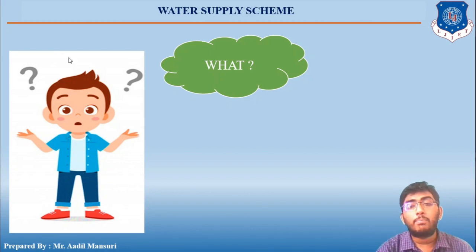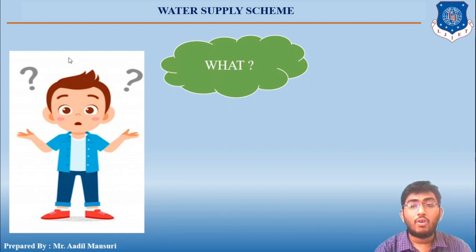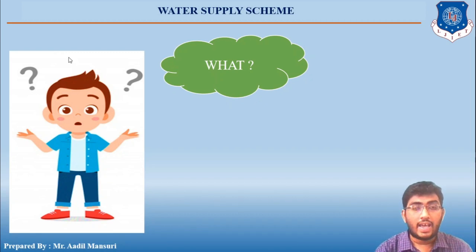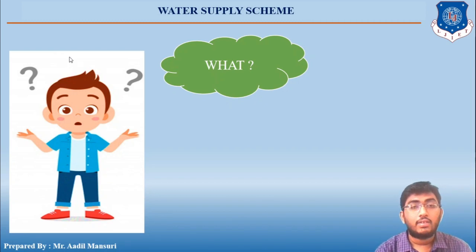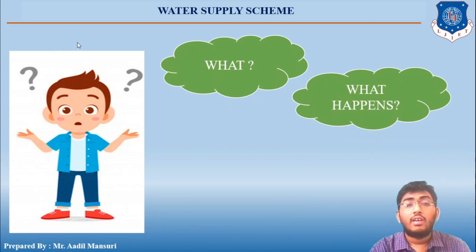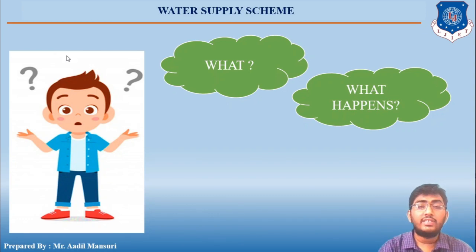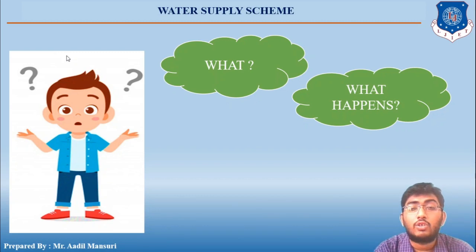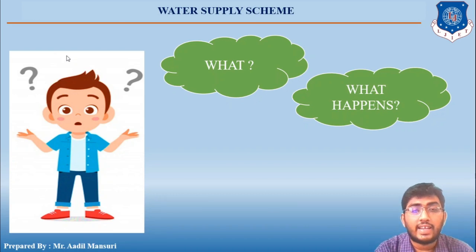Aeration is one of the important unit operations of a water treatment plant for gas transfer. When you bring water in contact with air, exchange of gases takes place. In the aeration process, water is brought in contact with air so that water will absorb oxygen present in air and will remove gases like carbon dioxide and H2S (hydrogen sulfide).